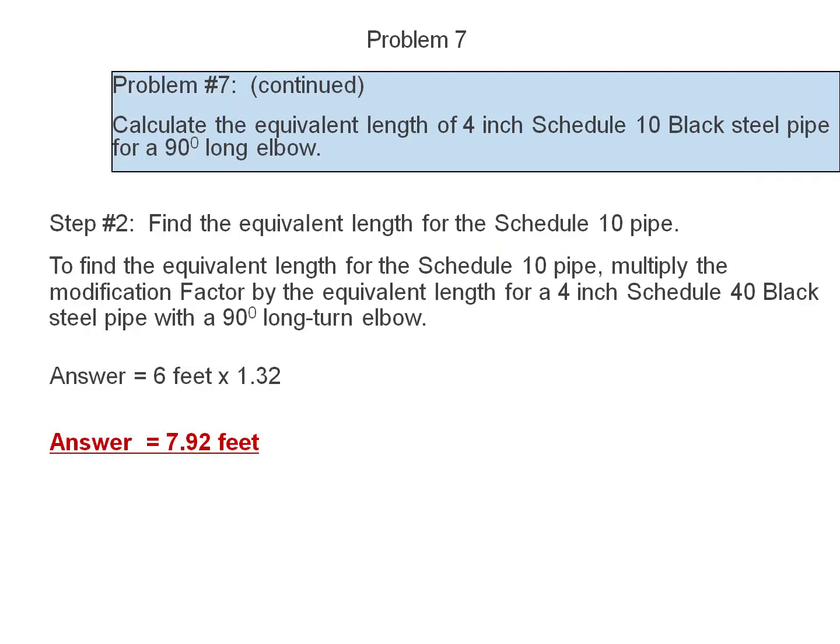Step 2. Find the equivalent length for the Schedule 10 pipe. To find the equivalent length for a Schedule 10 pipe, multiply the modification factor by the equivalent length for a 4 inch Schedule 40 black steel pipe with a long turn elbow. The answer is 6 feet times the factor of 1.32 will equal 7.92.